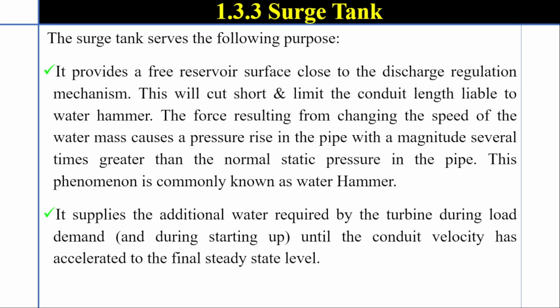It provides a free reservoir surface close to the discharge regulation mechanism. This will cut short and limit the conduit length liable to water hammer. The force resulting from changing the speed of the water mass causes a pressure rise in the pipe with a magnitude several times greater than the normal static pressure in the pipe. This phenomenon is commonly known as water hammer.